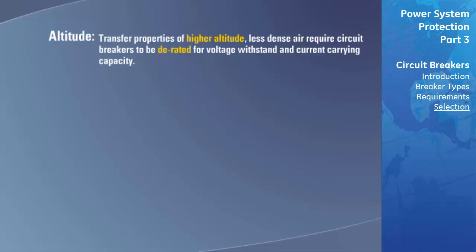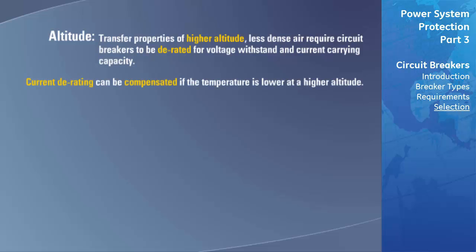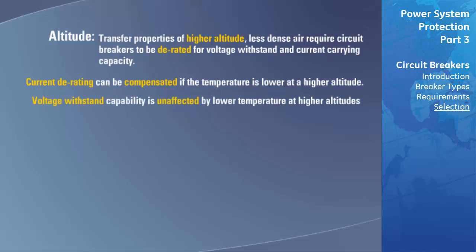As altitude increases, atmospheric pressure and air density decrease. The reduced insulation and heat transfer properties of less dense air require that circuit breakers be de-rated for voltage withstand and current-carrying capacity. Current de-rating can be compensated to some degree if the temperature at higher altitude is lower, but voltage withstand capability is essentially unaffected by lower temperatures at higher altitude.